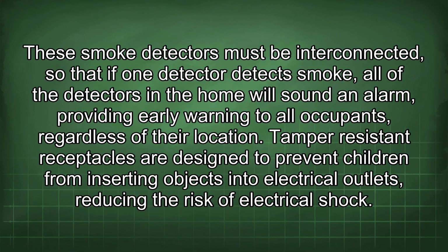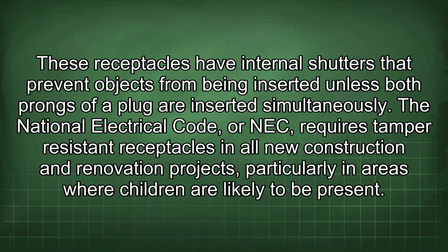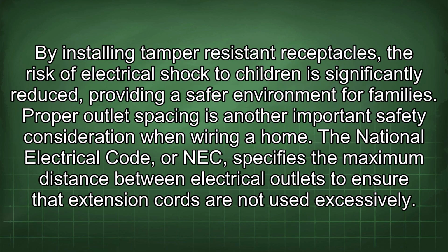Tamper-resistant receptacles are designed to prevent children from inserting objects into electrical outlets, reducing the risk of electrical shock. These receptacles have internal shutters that prevent objects from being inserted unless both prongs of a plug are inserted simultaneously. The National Electrical Code, or NEC, requires tamper-resistant receptacles in all new construction and renovation projects, particularly in areas where children are likely to be present. By installing tamper-resistant receptacles, the risk of electrical shock to children is significantly reduced, providing a safer environment for families.